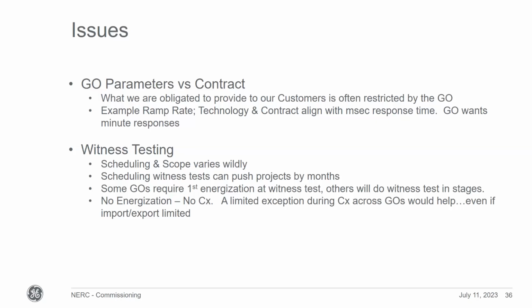The other area is witness testing. We find the scheduling and scope varies wildly, and scheduling these witness tests can push projects by months. There's no self-test or self-submittal on these witness tests. Some grid operators require first energization at the witness test, meaning we've had no chance to test our equipment beforehand. Other grid operators understand that and do the final witness test at a later stage.